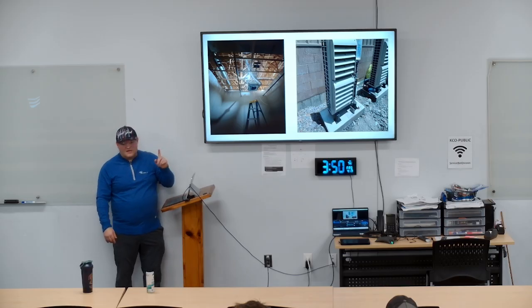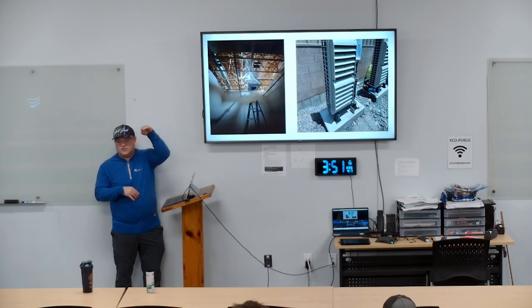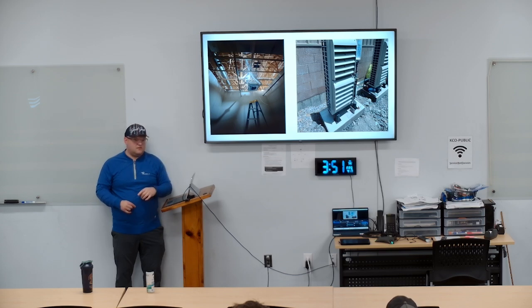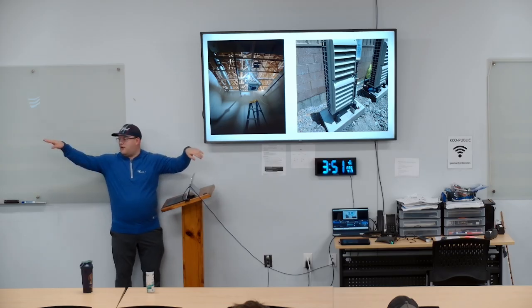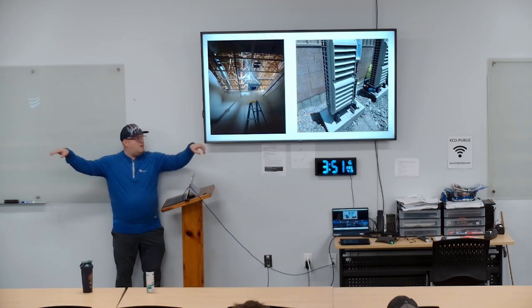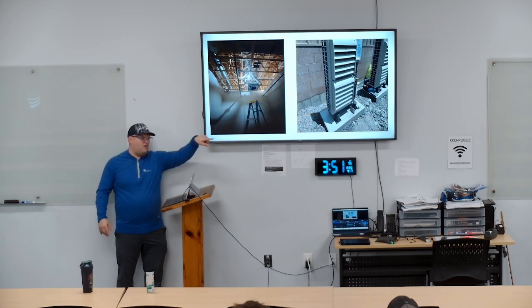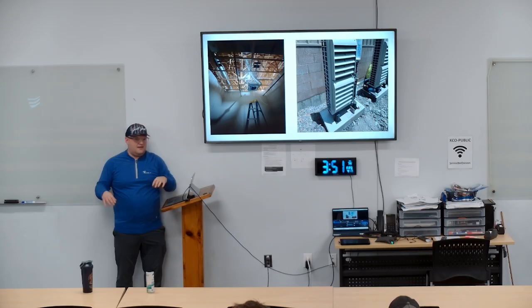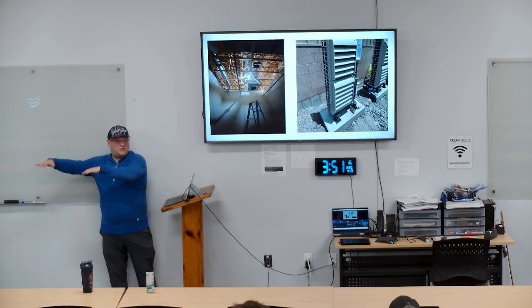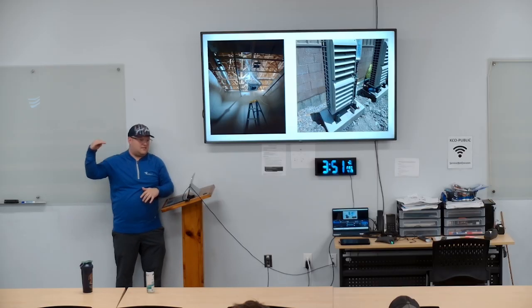So with that being said, those units can only normally pump. They say, oh yeah, they can pump 26 inches. That's from the face of the unit. So when it's all said and done, we only got 14 that we can come up off that unit. So keep that in mind. We've had some instances where guys are like, oh, well, this one down here, we're gonna have a ceiling height at 8, and that one down there, we're gonna have a ceiling height at 10, but it's all gonna run from there down or from there back. And it doesn't add up because the ceiling height's changed down through it, and we couldn't get our condensate to flow.